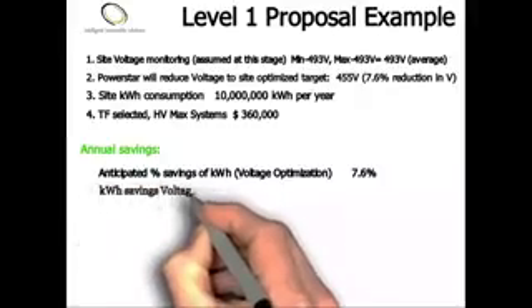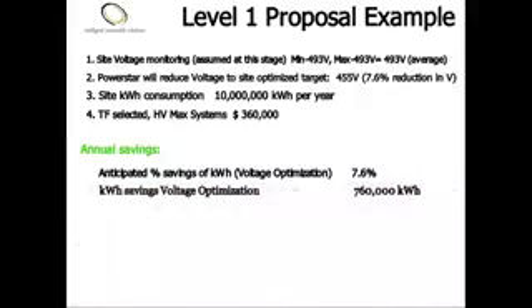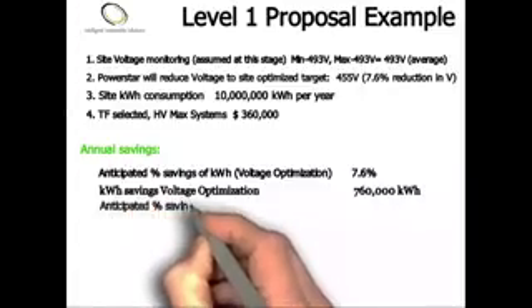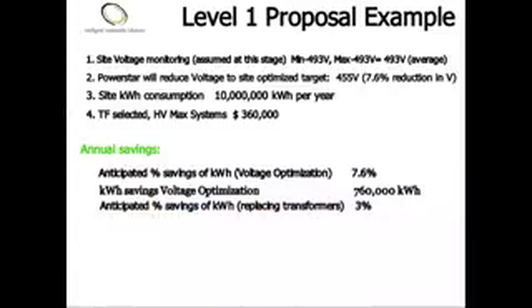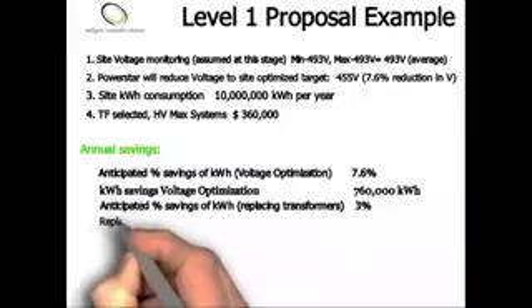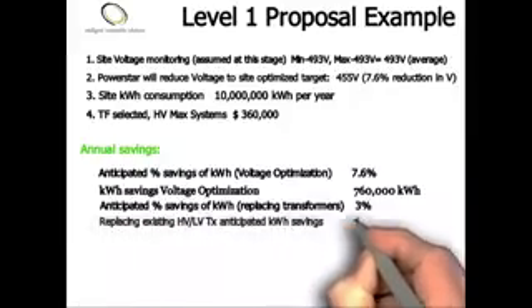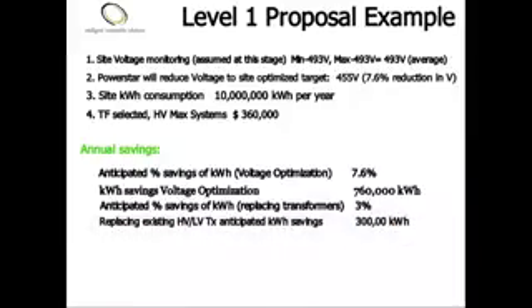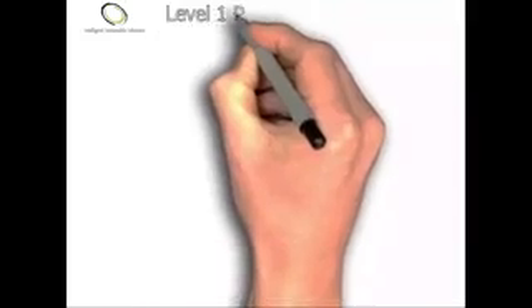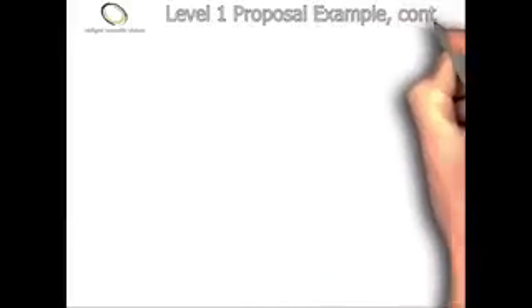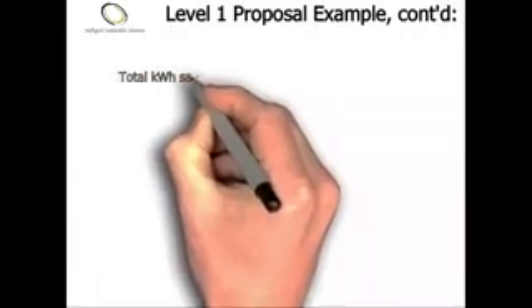Anticipated percent savings, as we stated above, of 7.6%. This comes from the voltage regulation when PowerStar Max is installed. This equates to 760,000 kilowatt-hours. The anticipated percent savings from the high-efficiency amorphous core super low-loss transformer is assumed at 3%. This equates to an additional 300,000 kilowatt-hours. To summarize the proposal, we therefore have a total of 1,060,000 kilowatt-hours in savings.